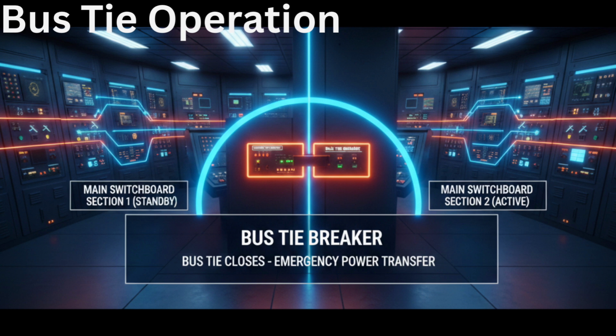However, before closing the bus tie, proper synchronization must be ensured. Electrical interlocks are provided to prevent incorrect operation. Bus tie operation improves redundancy and system stability.